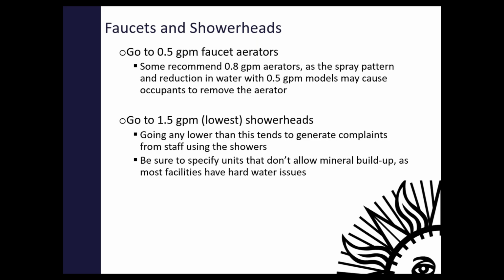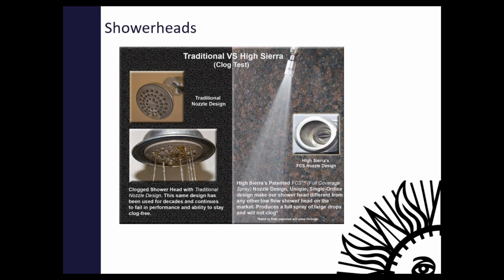Shower heads, you can go down to 1.25 GPM. I wouldn't recommend it. I tried it. I didn't much enjoy it. I have a 1.5 GPM shower head installed in my place, and it works just fine. I guess one thing you have to be aware of when you specify low flow fixtures is the hardness of your water. You don't want to recommend a low flow fixture only to have it clogged up because there's no proper filtration at your site.